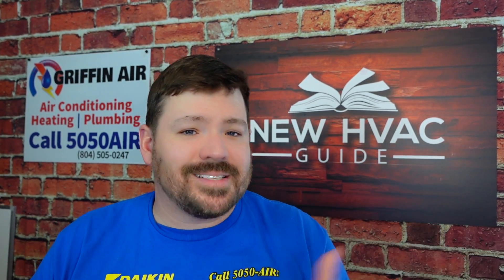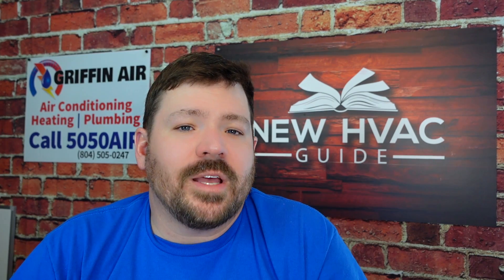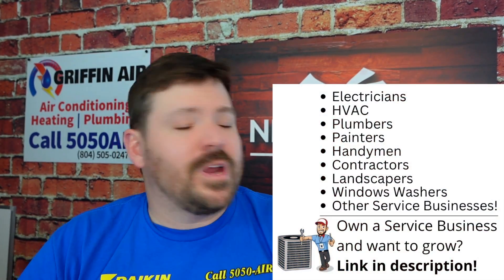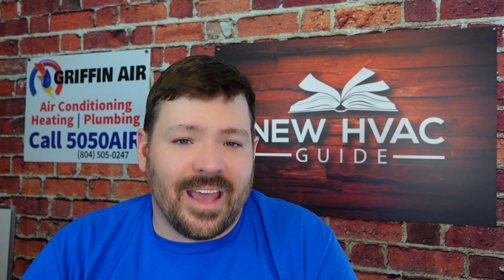I found in big bold letters right there in the instructions how the low voltage wiring needed to be wired depending on what type of system it was set up with. Had the guy that installed that system read those instructions, this poor homeowner would not have been without heat on a holiday. Luckily we got that straightened out, but if the original installer or any service tech after that had taken a moment to read the instructions — they were laying right on top of the furnace — they would have found it quickly because it was written in big bold letters.